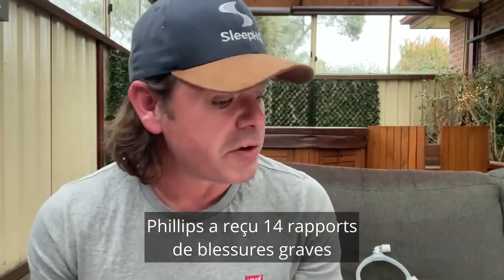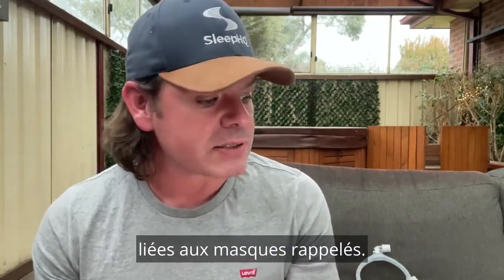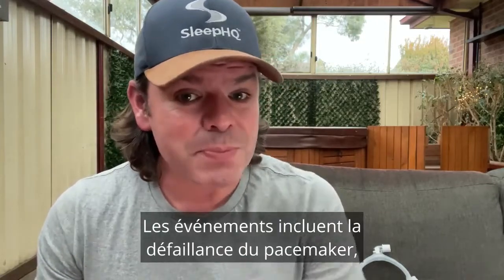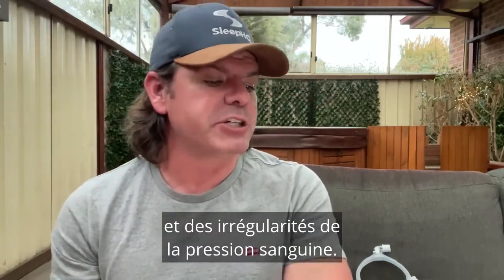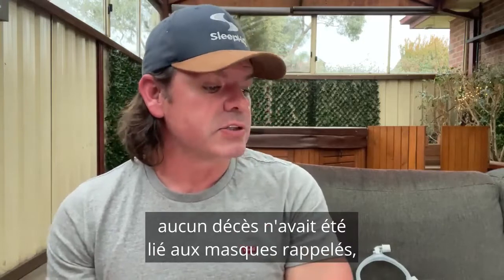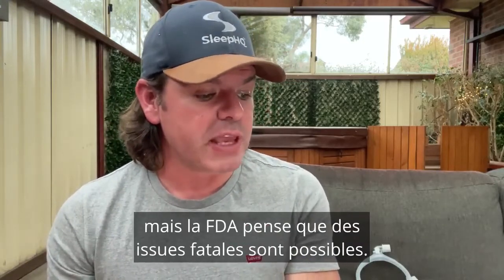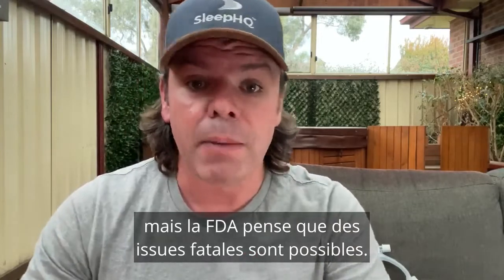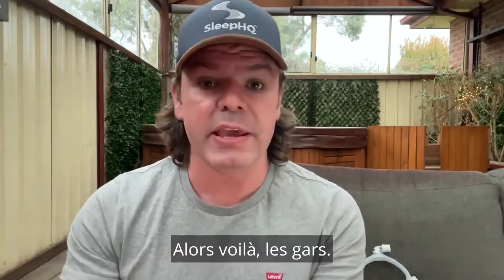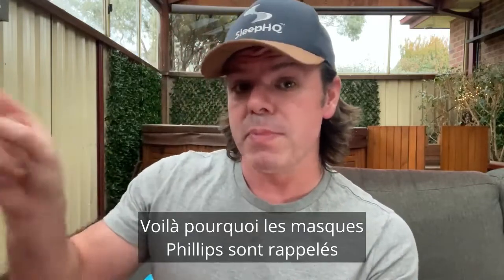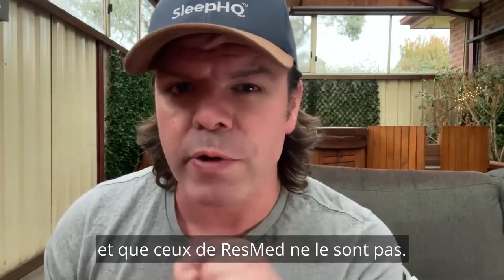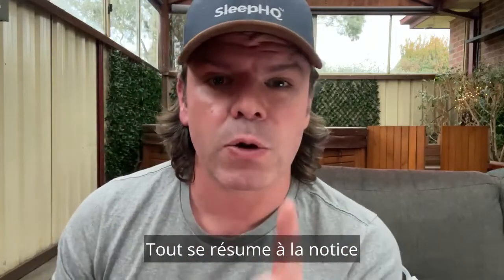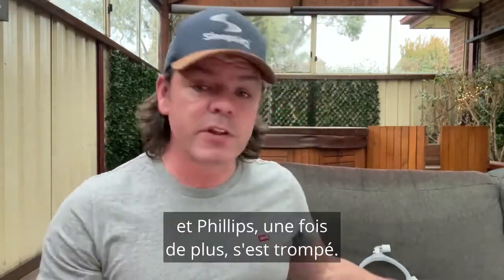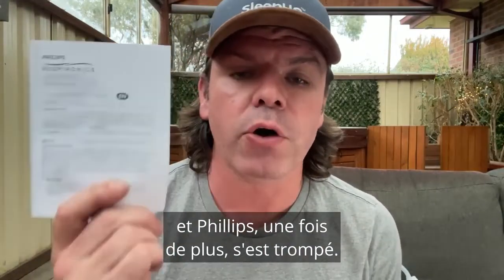And to date, Philips had received 14 reports of serious injuries related to the recalled masks. The events include pacemaker failure, arrhythmia, seizures, and irregular blood pressure. No deaths had been linked to recalled masks as of last week, but the FDA thinks fatal outcomes are possible. So there you go, guys. That's the reason the Philips masks are being recalled and the ResMeds are not being recalled, all right? It all comes down to the documentation, and Philips, once again, they got it wrong.